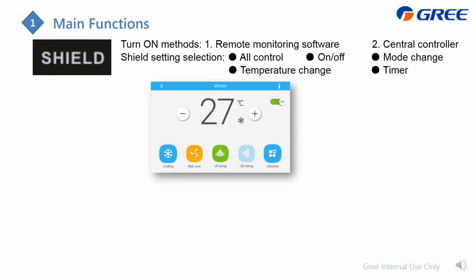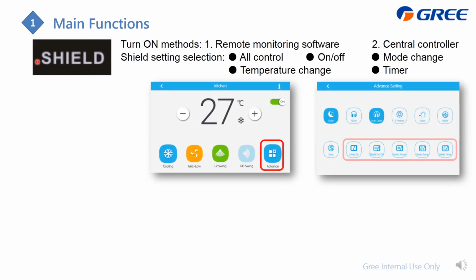Shield function, also called blocking the setting from the wire controller. Here is the turn on method. You can set it from the remote monitoring software or from this central controller. From here, you first select the specific indoor unit. Then from this advanced setting, we offer you this function, which can control all of the settings, such as turning this indoor unit on or off, changing the mode, changing the temperature, or using the timer.